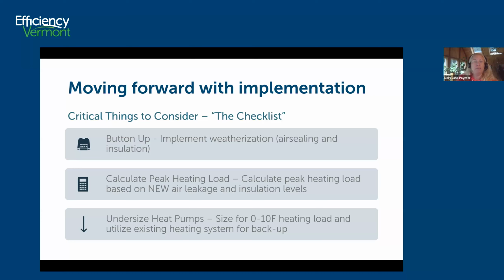And then because your building has a backup heating system, here's an opportunity to undersize the heat pumps so that you can utilize the backup heating system and not have to install so many units or upsize the units in order to handle the really cold temperatures. Because you do lose some capacity as you get down into the colder temperatures. And I'll show you some graphs of that.